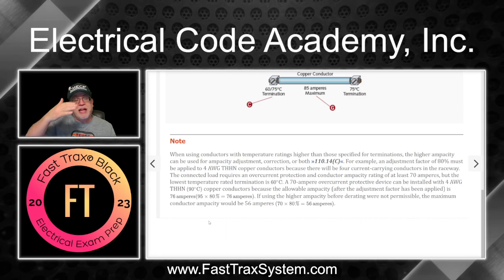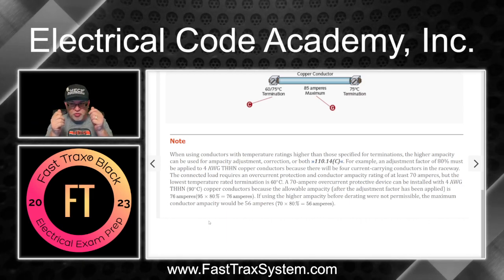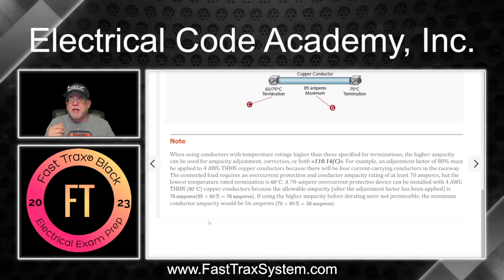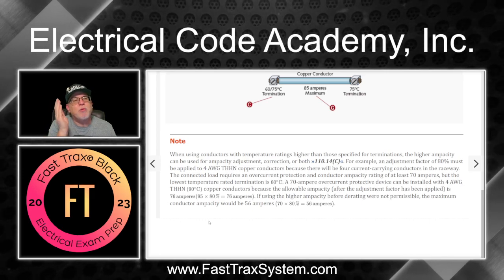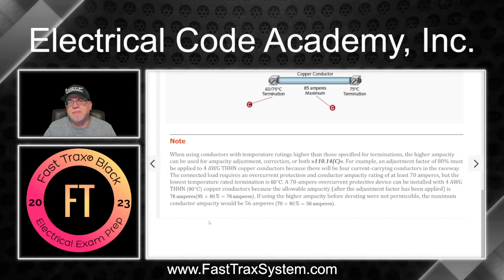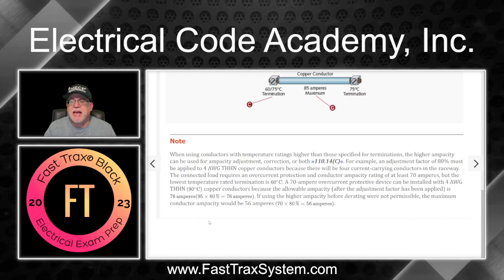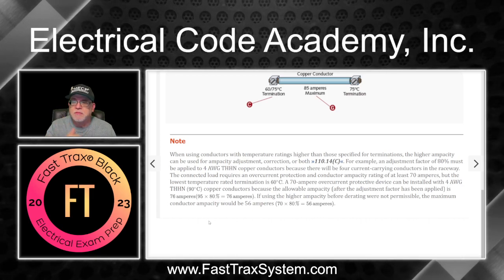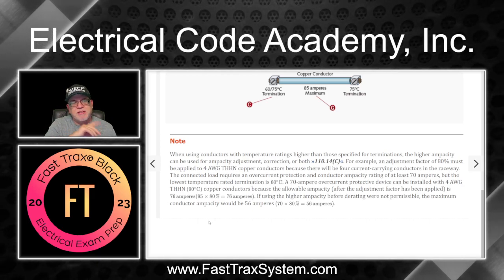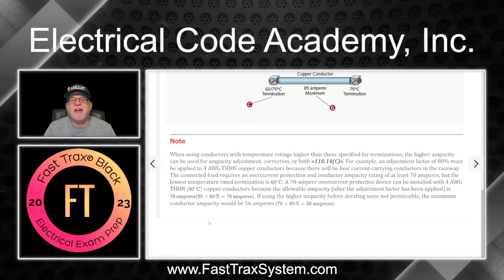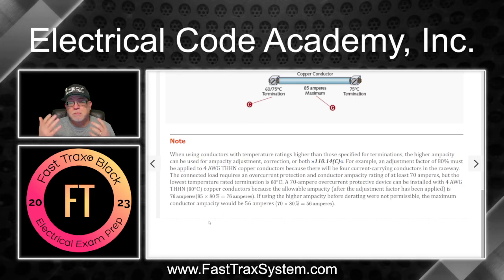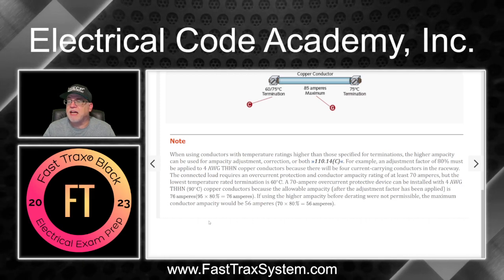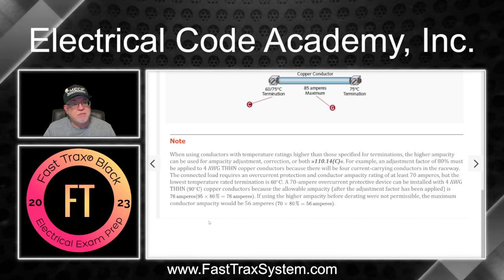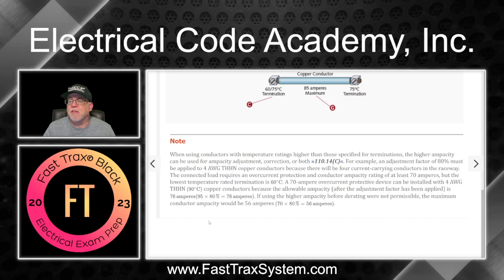So we were able to use that 95, remember, that's what the conductor's rated at, 90 degrees C, 95, and then we multiply that by 80%. When we multiply that by 80% or 0.80, got to convert it into a decimal, makes it easier to do the math, that equals 76 amps. Well, 76 amps is fine. It's still higher than 70, not a problem, no harm, no foul, right?